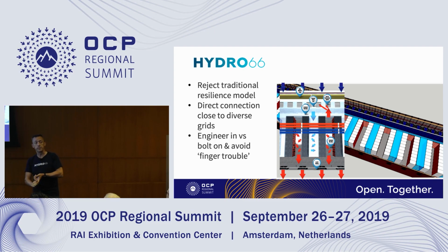So we have no DX expansion, we have no external chillers, and that gets our PUE down. On-prem is typically two times PUE; efficient is 1.5 PUE; Equinix best case for DX indirect is 1.2 PUE. This data center, which I think is why we won the DCD award last year, is 1.07 PUE, and it's 100% renewable.